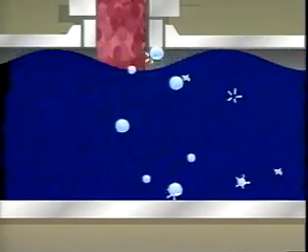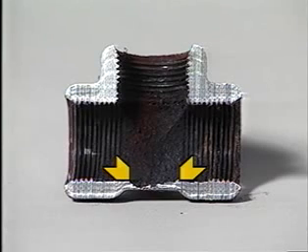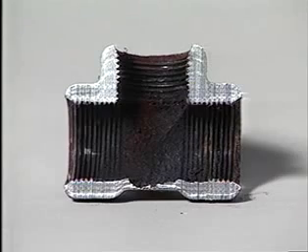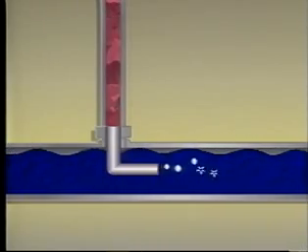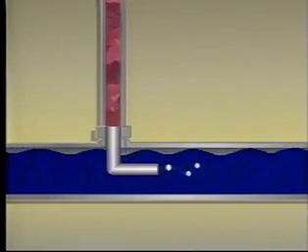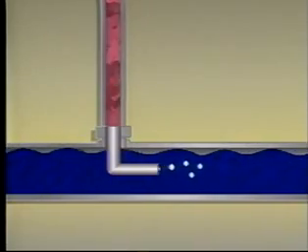The localized sudden reduction in pressure near the wall chips away piping and tube interiors. Oxide layers that otherwise would resist further corrosion are removed, resulting in accelerated deterioration of piping and equipment. To minimize such a disturbance, the drip trap should discharge in the direction of condensate flow by means of a special fitting. This method of controlling thermal shock, called sparging, reduces the concentration of collapsing steam bubbles and keeps the action from occurring by the pipe wall.